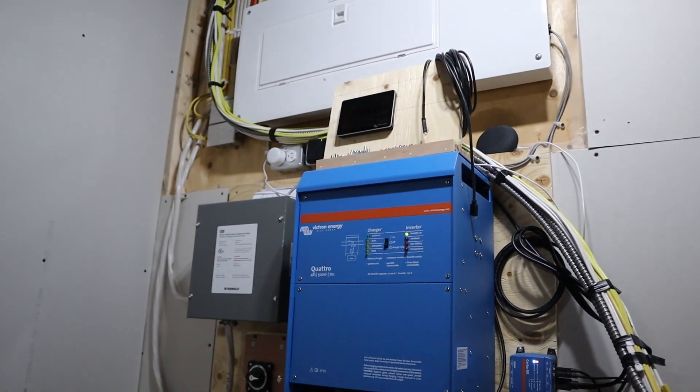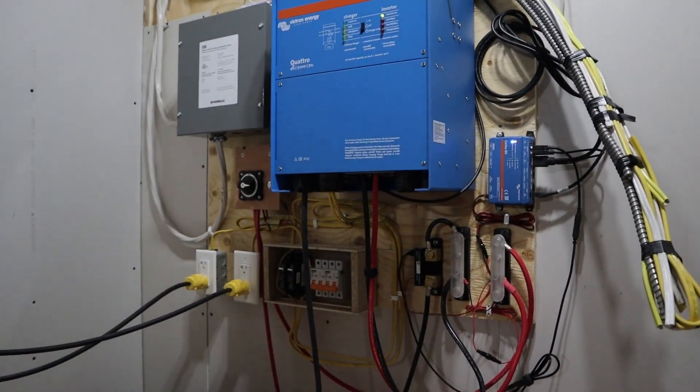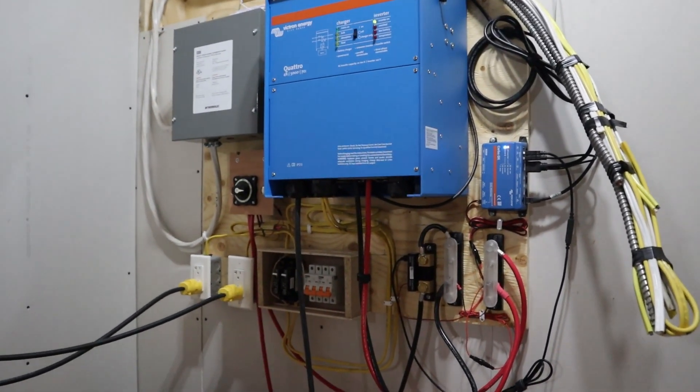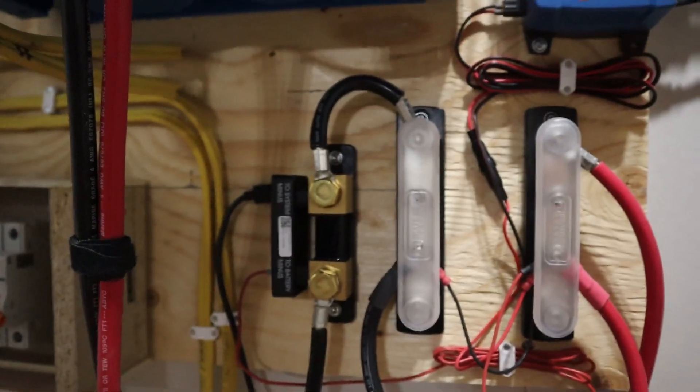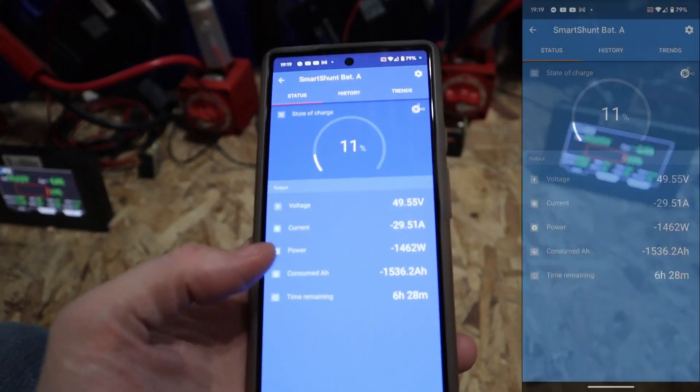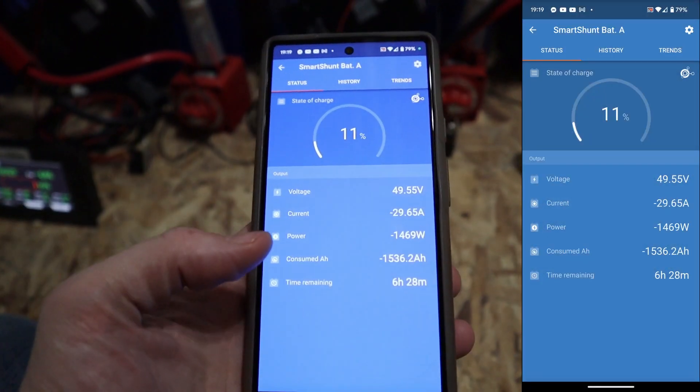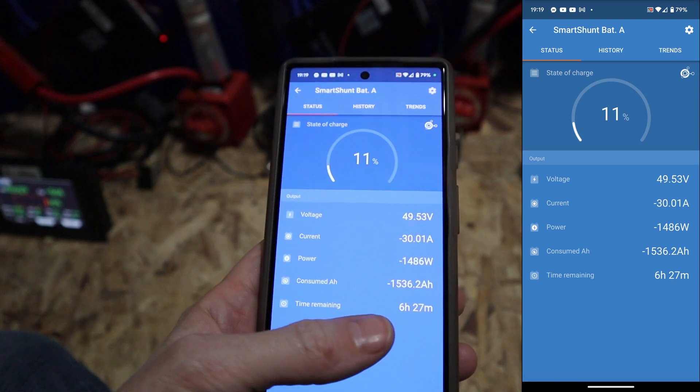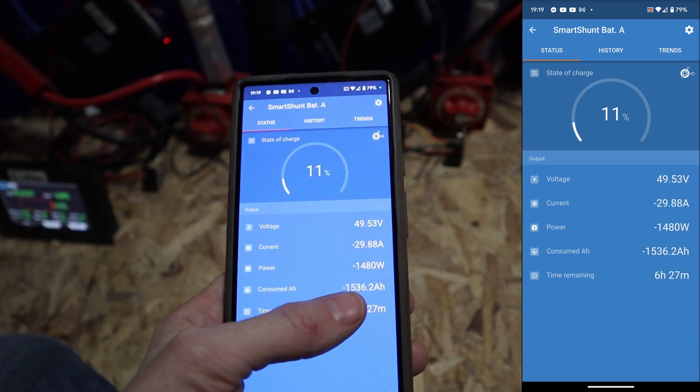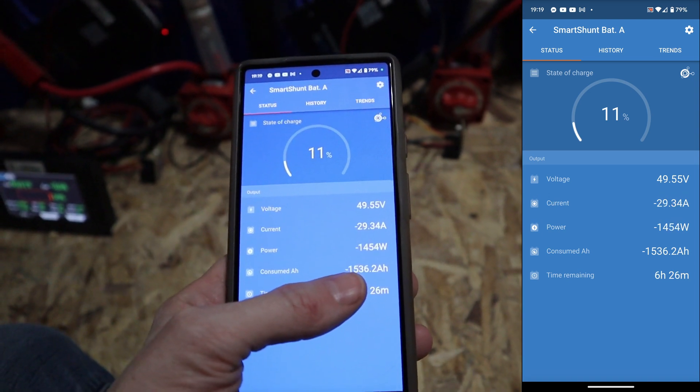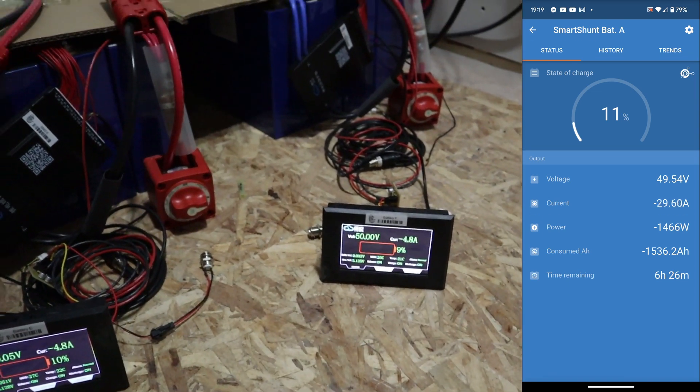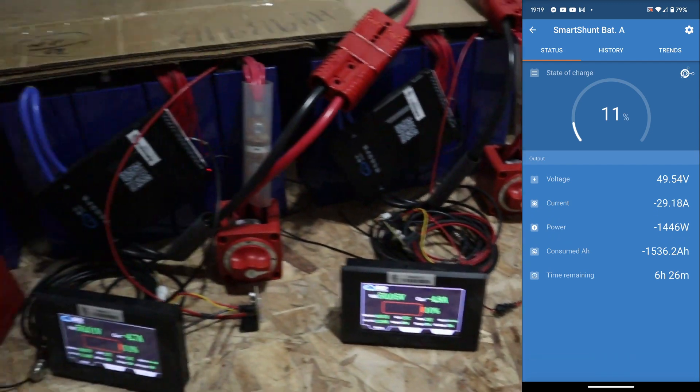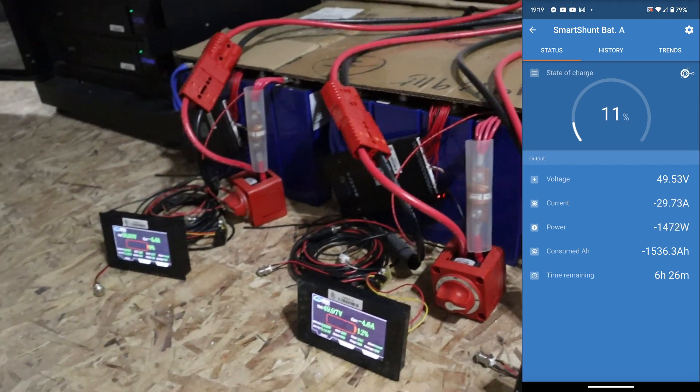The smart shunt and the Quattro, therefore the VRM, is only showing the power that is passed through the smart shunt. The smart shunt has shown that I have discharged 1536.2 amp hours, but that is missing any parasitic draws inside of the BMSs themselves.